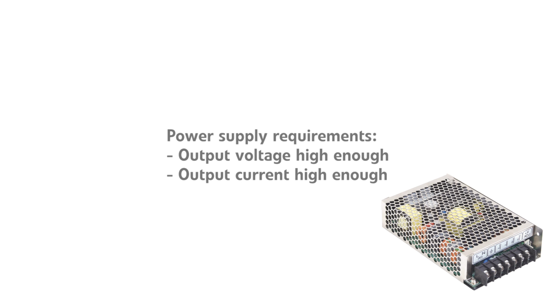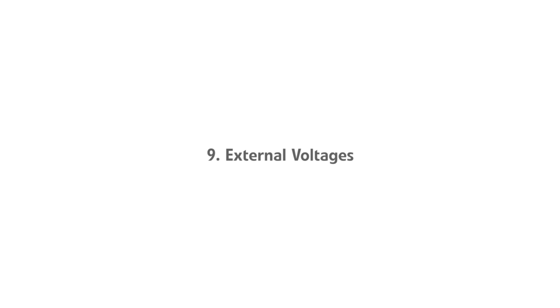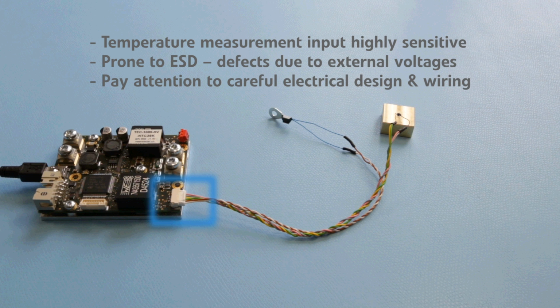The requirements for power supplies to drive the TEC controllers are simple. The voltage should be high enough and the supply just needs to have an output current high enough for the controller. Otherwise, when the power supply is in its limitation, the controller will shut down with an error. The temperature measurement input of our TEC controllers is highly sensitive to achieve a high measurement precision. However, this makes the input also prone to defects caused by external voltages. Therefore, when integrating the cooling application into a system, one must pay attention to a careful electrical design and wiring.